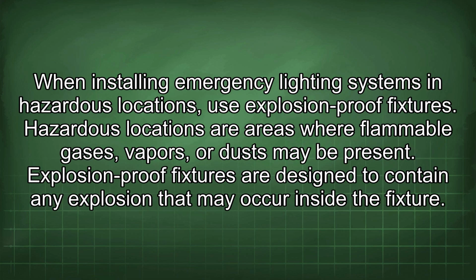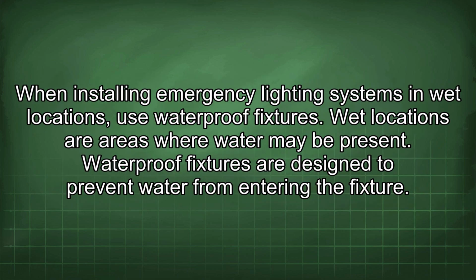When installing emergency lighting systems in hazardous locations, use explosion-proof fixtures. Hazardous locations are areas where flammable gases, vapors, or dust may be present. Explosion-proof fixtures are designed to contain any explosion that may occur inside the fixture. When installing emergency lighting systems in wet locations, use waterproof fixtures. Wet locations are areas where water may be present. Waterproof fixtures are designed to prevent water from entering the fixture.